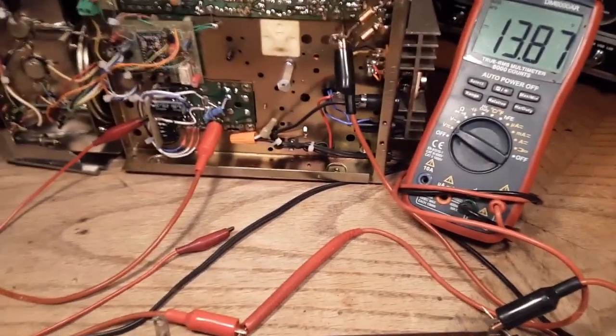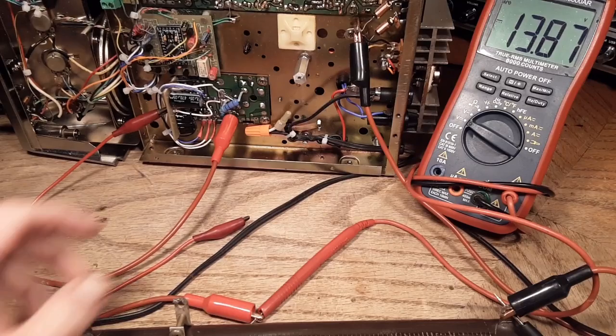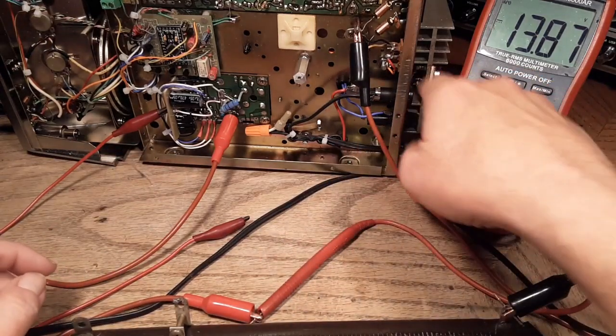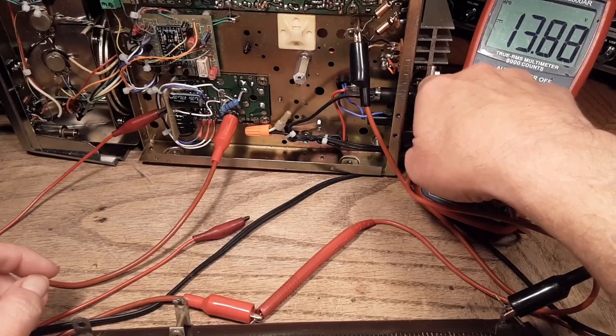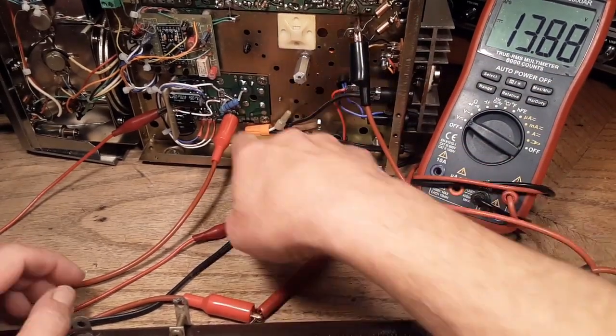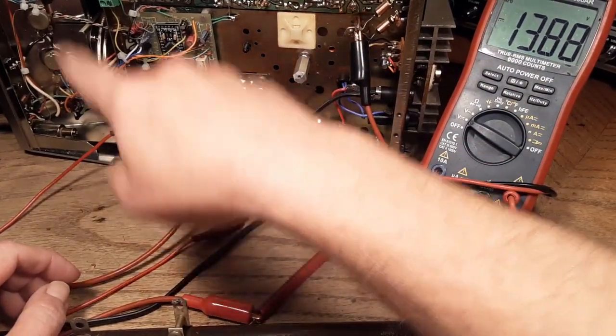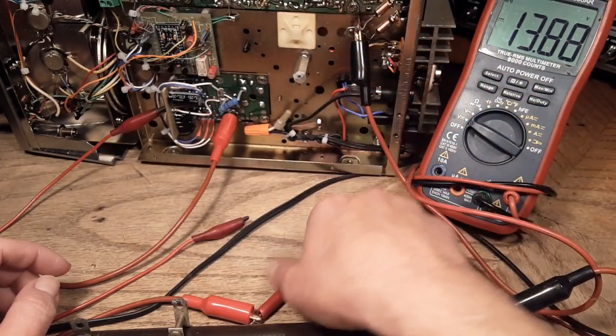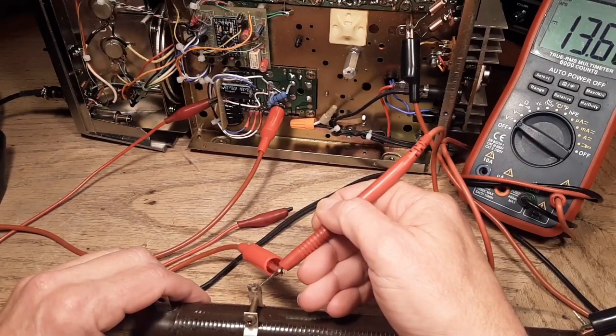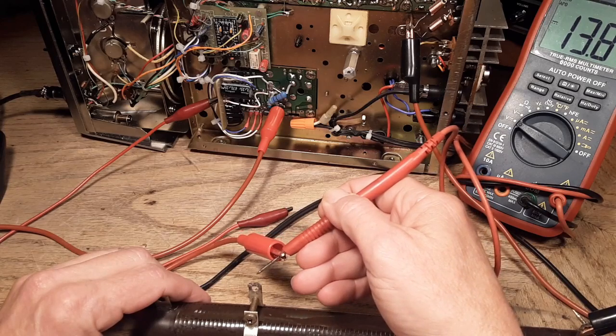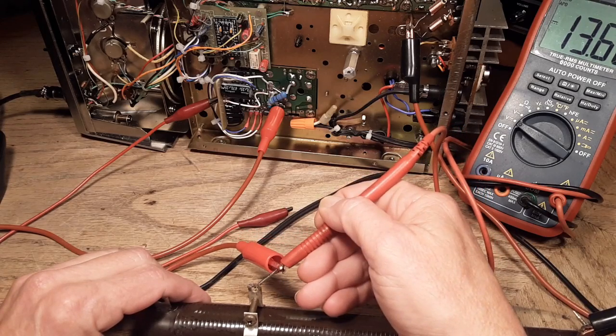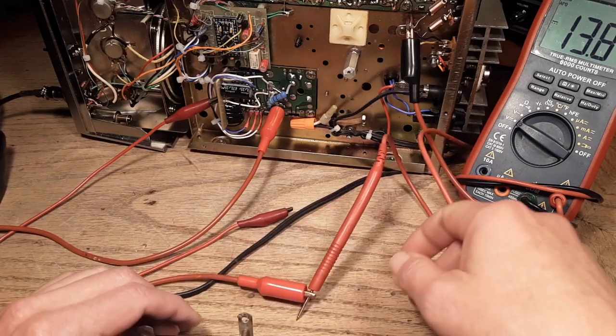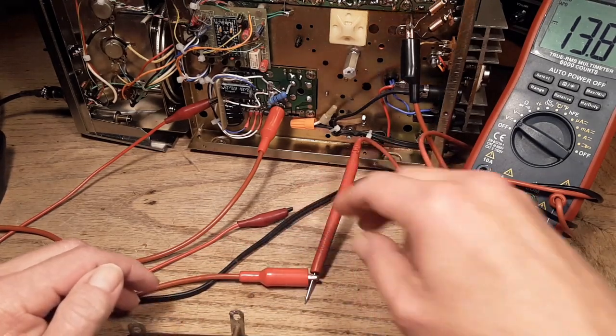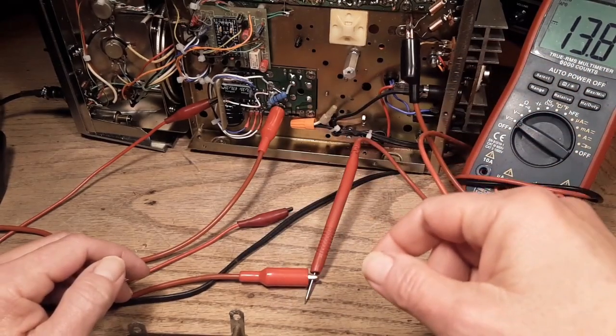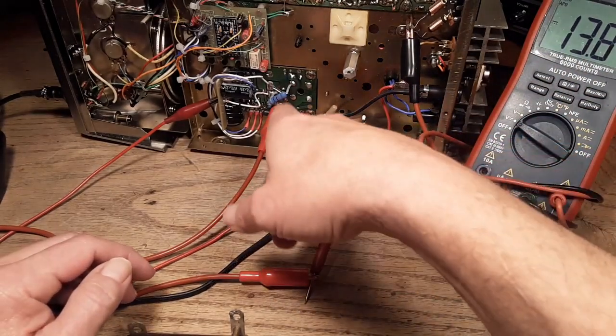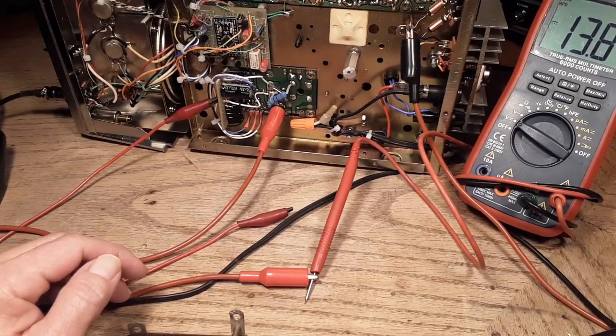So if we plug this guy in, we get 13.87 coming out of it. I'm basically connected on the emitter of this pass transistor here, where it comes up and goes onto the regulator to put power throughout the radio. If I put a 3.5 amp load on there, it drops from about 13.88 to about 13.6. That's pretty acceptable because there are voltage drops on the wires here and such. And those regulators, the way they're made, they're not great to start with.